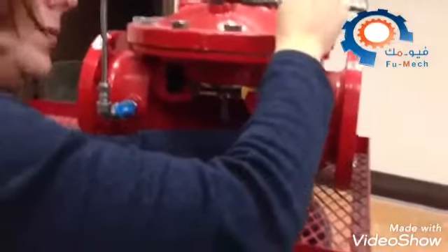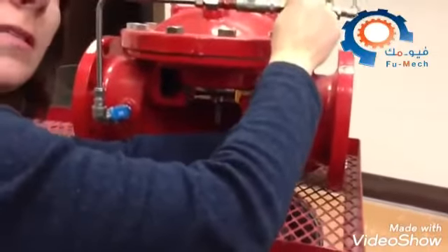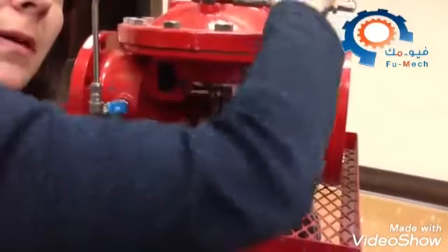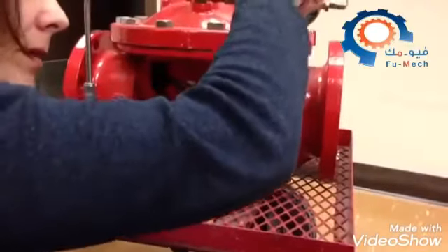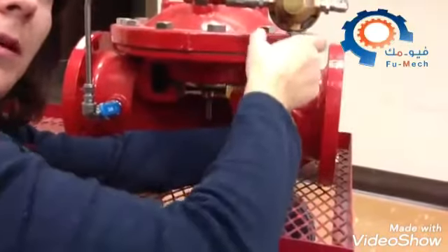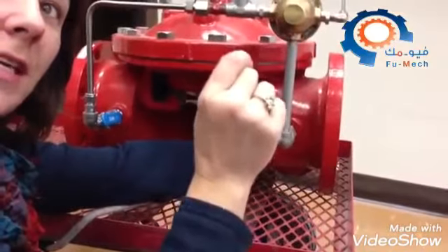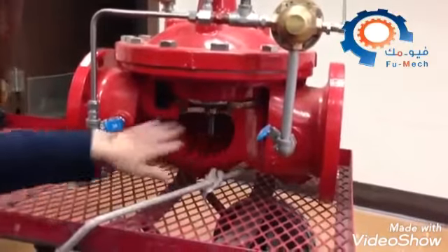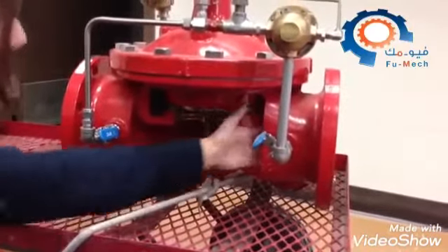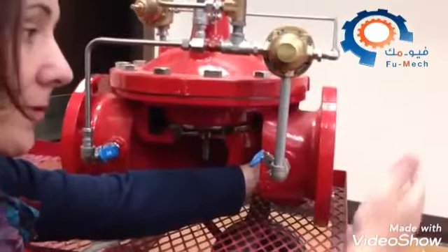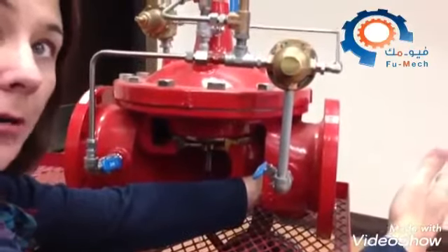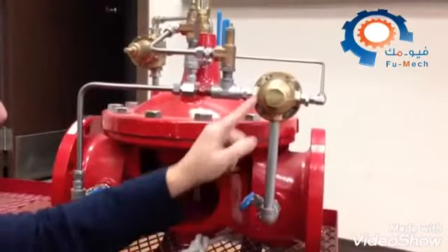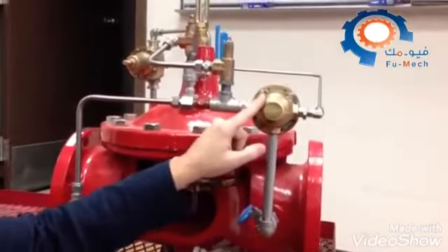Yep. So when we have a high pressure situation in here, because this is a reverse seated valve, it forces the stem to travel up, which lifts the saddle assembly up, which brings the disc closer to the seat, which closes the valve. So if this pressure rises too high, and that will happen when your downstream users stop using water and that closes, this pressure will build in here. That high pressure will be transmitted in here, and then this valve will start to close.